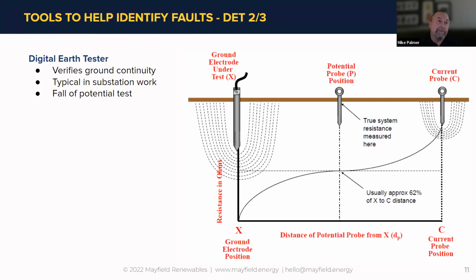the inverter side usually. With which the NEC code states 25 ohms or less, correct? So, correct. You're going to need to figure out how to get to that 25 ohms. So typically, what every contractor is going to do is a fall of potential test, and really what you're looking at here is the electrode there on the left, which is the one either feeding the bus bar ground location in the inverter, and you're going to put one test lead on that. You're going to stagger the test leads out given the area you have to work with, because as we know, the footprints sometimes are limited in and around the inverter.